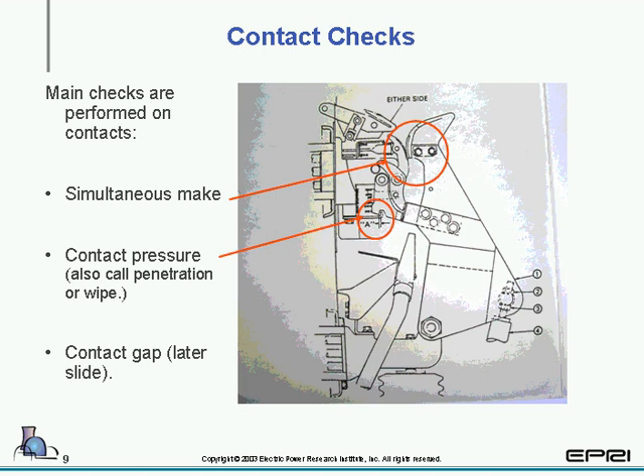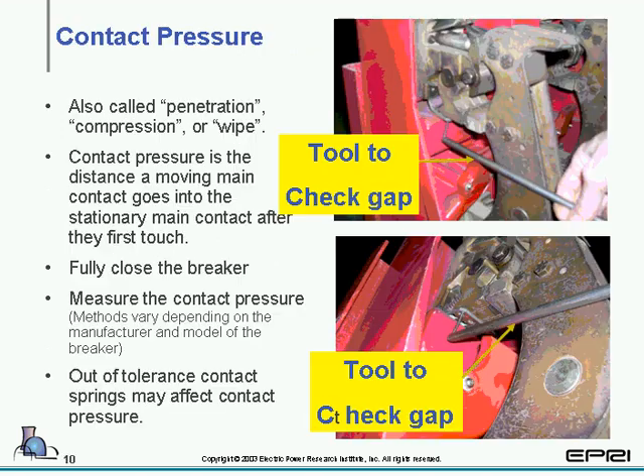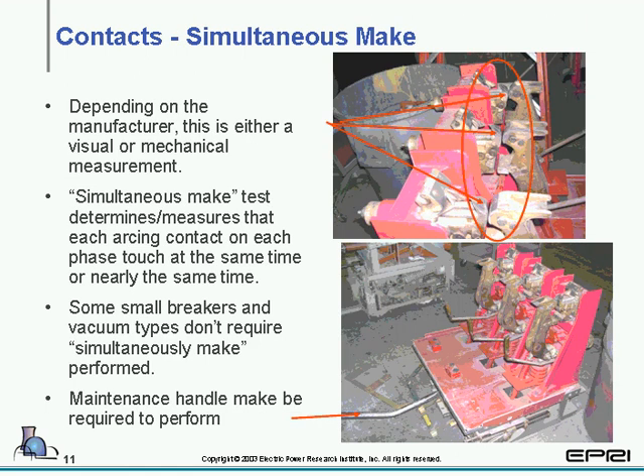One that is usually typical of all breakers is main contacts, is simultaneous make and contact pressure, also called penetration or wipe. And we're taking a look at this at next slide. First we're going to take a look at is contact pressure. It's also called penetration or wipe. Contact pressure is a distance the moving main contact goes into the stationary main contact after they first touch, hence penetration. And you're going to see we have two slides with this particular manufacturer.